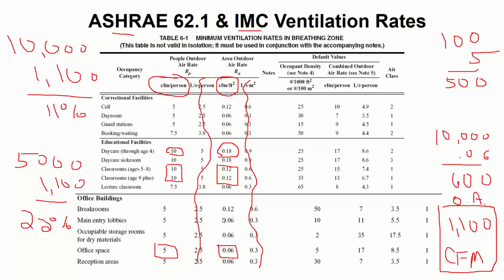So your thermostat absolutely positively has to be in the on function during all building occupied hours. And then at nighttime, it could be in auto. Auto means it only turns the fan on if there's a need for heating and cooling. On means the fan is on all the time. So during the day, let's just say you have a normal office building. It's open from 7 a.m. to 6 p.m. So at 7 a.m., the fan needs to turn on, and the ventilation damper needs to go, in our example, to 1,100 CFM opening to bring fresh air in. And then at 6 p.m., that damper should go shut and stay shut all night long because no one's there.